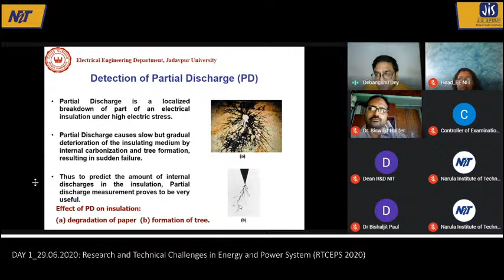You can easily understand that if this goes on happening, say 24 hours, inside the insulation, it will damage the insulation. So the effect of PD, or partial discharge, on insulation is that it will degrade the paper, and there can be formation of tree-like structures that will gradually cause complete breakdown. So for condition monitoring of a particular electrical equipment, say a transformer, this kind of partial discharge signal is also very important. If you find some partial discharge signal, you should be very careful about it and try to mitigate it.